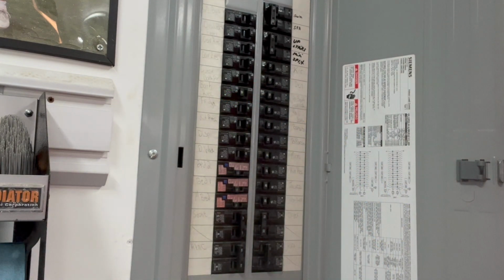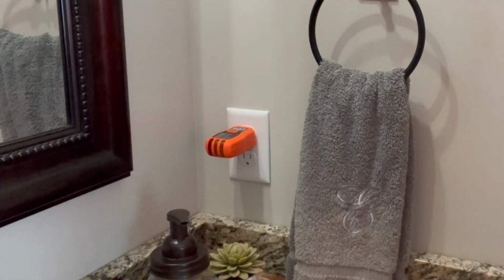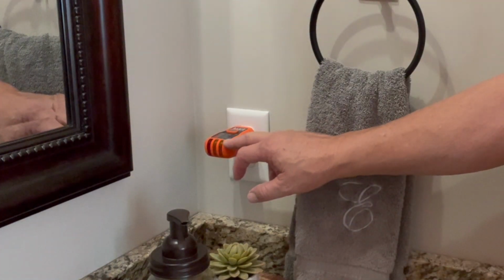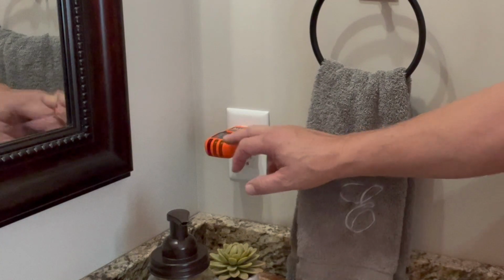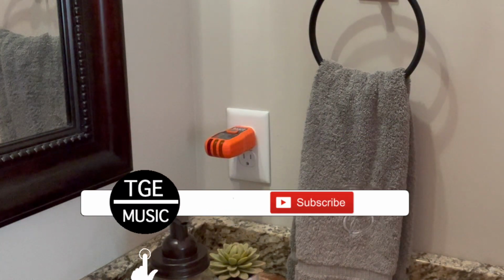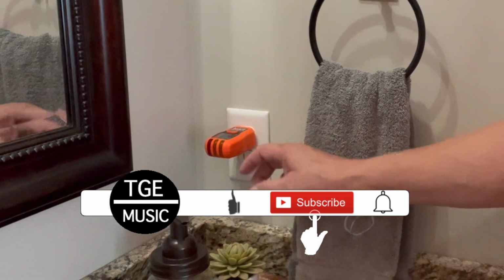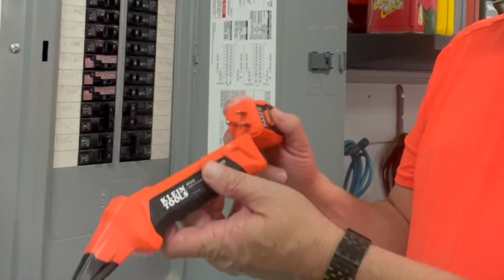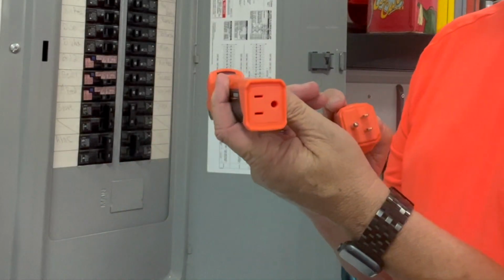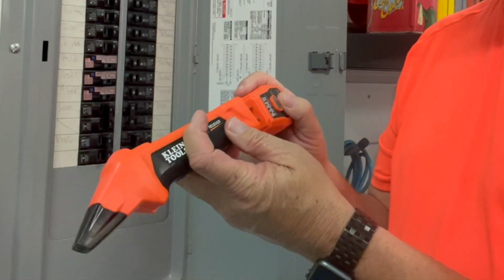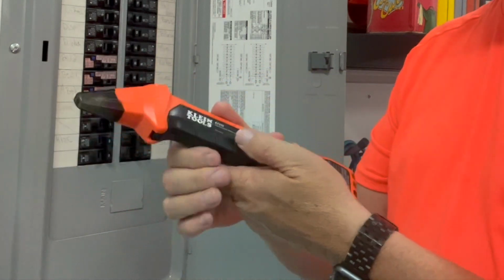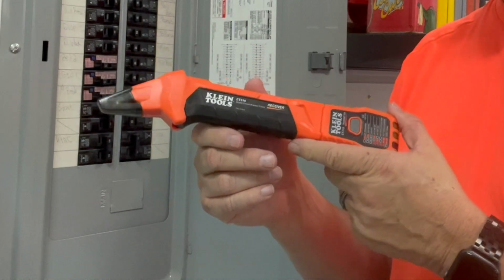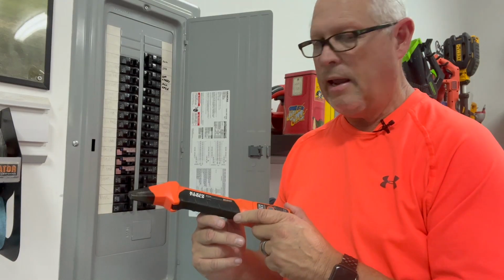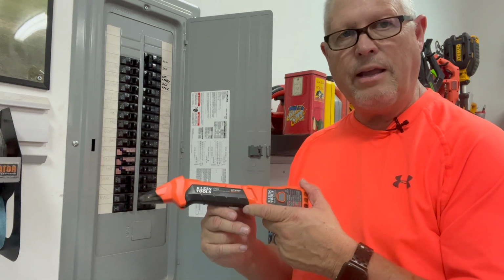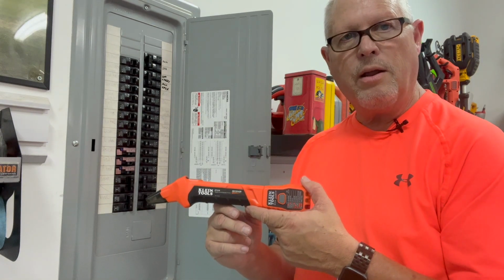Okay, we'll turn it off and let's verify if we got the correct circuit. So as you can see, we got the correct circuit breaker tripped to indicate that that's the correct circuit there. And again, you have the ground fault here that you can test as well, but we won't do that again. Okay, you just return the transmitter back into the end of the receiver here. It just plugs into that for easy storage to make sure you don't lose it. As you can see, it works very effectively, and I would recommend the Klein Tool ET310 for your circuit breaker tracer.